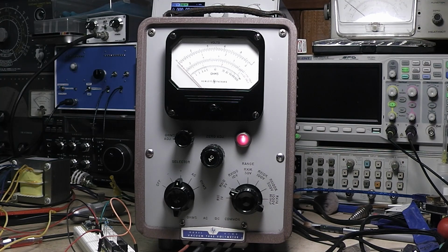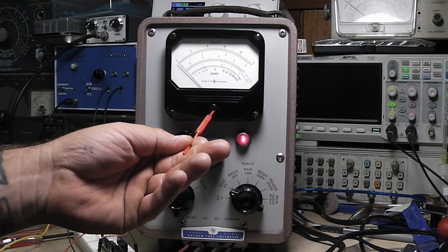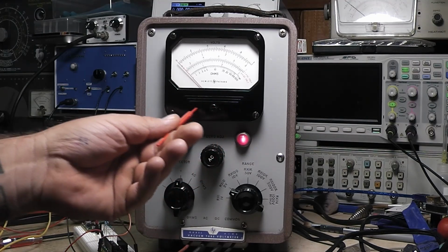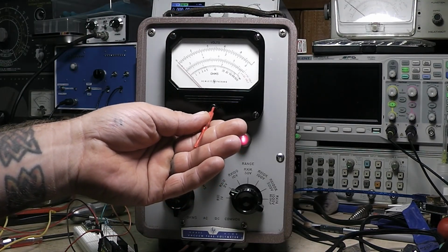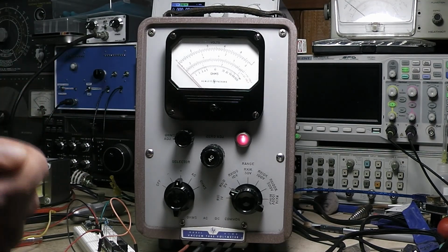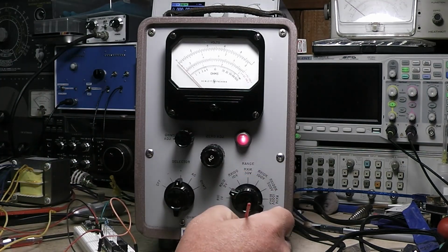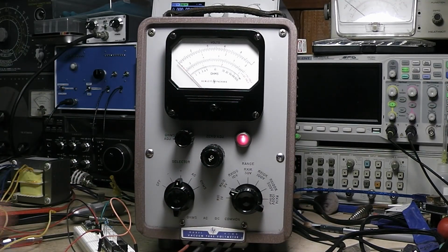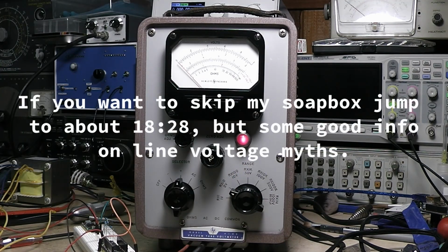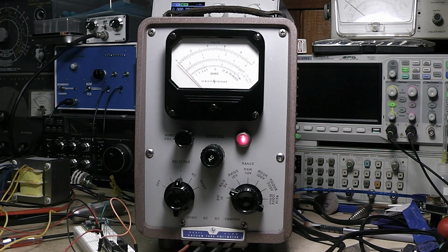I've had this thing warming up for a while. Now, one thing I do want to mention, you want to do before you plug it in, with the unit unplugged, this is any type of instrument like this, is this zero set here on the face of the meter itself. Adjust that counterweight that's in there. This here you want to adjust. You might not want to use a soft plastic like this, but you want to adjust this with it unplugged. Make sure it's dead on zero. And then plug it in, let it warm up, and get ready for the calibration. Okay. And when you're doing your calibration, you're like, well, what do I use? If you've got the means, a facility that's got the really high dollar calibration stuff, that's great, use it.